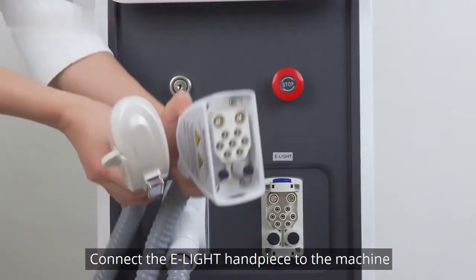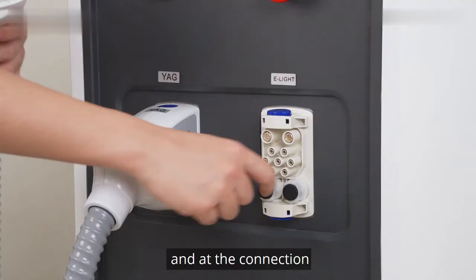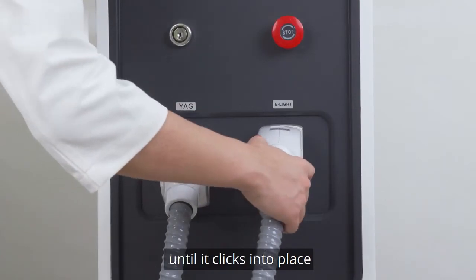Connect the E-LIGHT handpiece to the machine. Remove the black rubber caps on the connector and add the connection. Insert the connector aligned with the small holes and push the connection until it clicks into place.